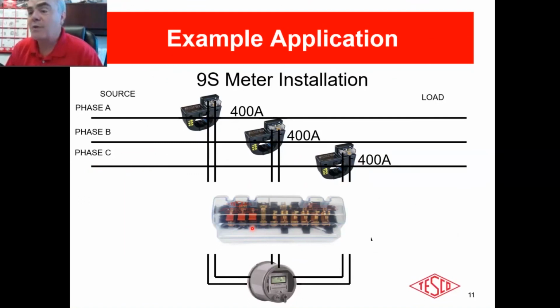The test switch itself is actually a really clever device that allows you to very safely bypass and reconnect the metering circuit to the service. We talked about that. We had a whole presentation on them last week, so I won't bore you too much, but test switches have been around for a very long time. We celebrated their 100th anniversary this summer in August. That's when the patent was awarded. They were actually in service a few years before that and actively used by many utilities. It's a knife blade switch. Knife blade switches went out of vogue in the 1920s. But it's a very safe, very clever design, and there's a massive infrastructure.